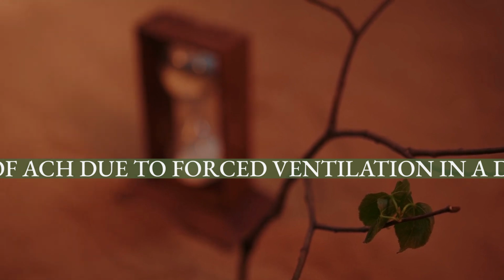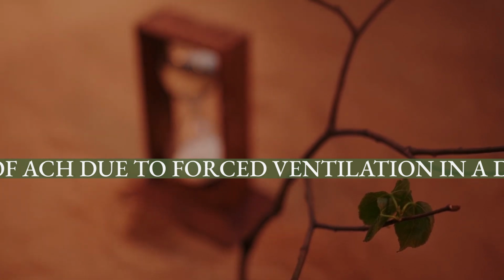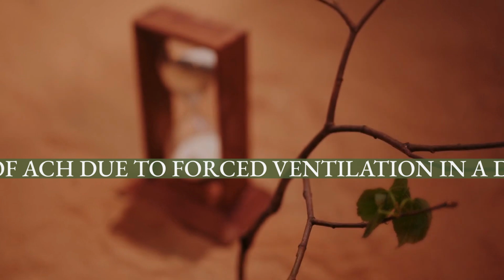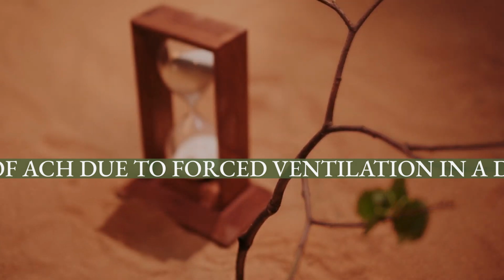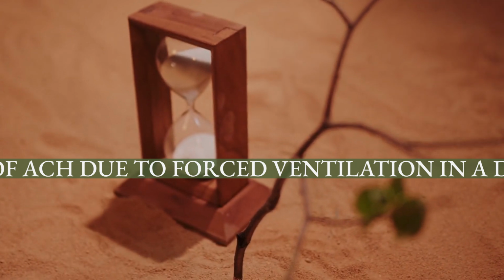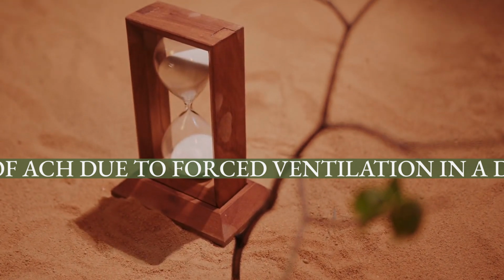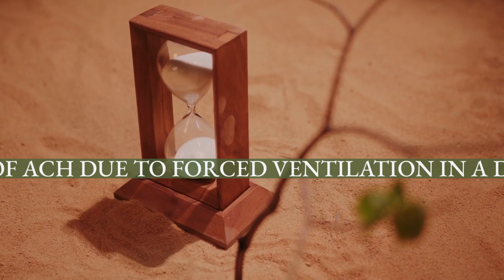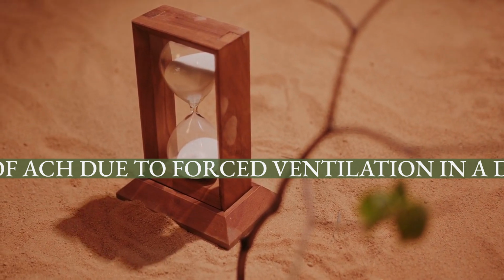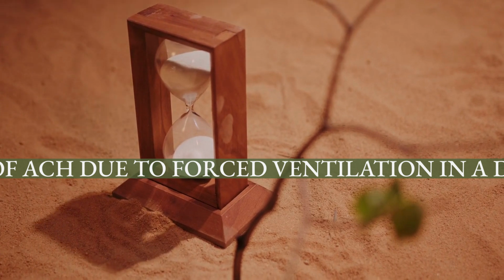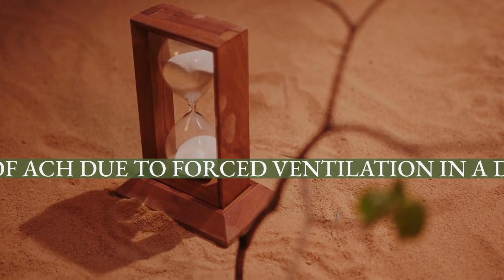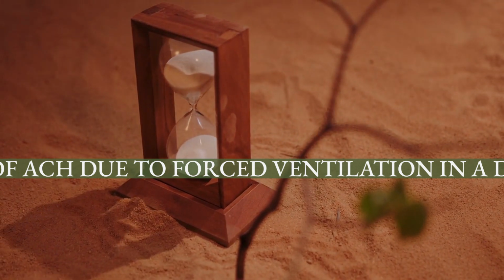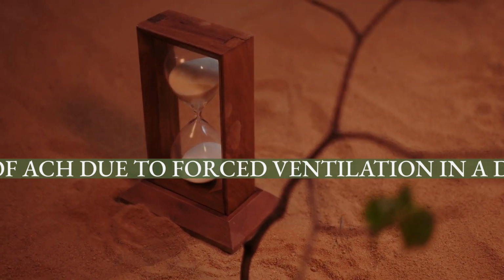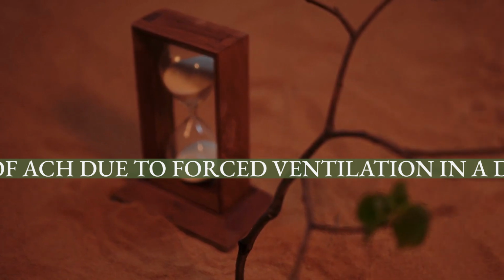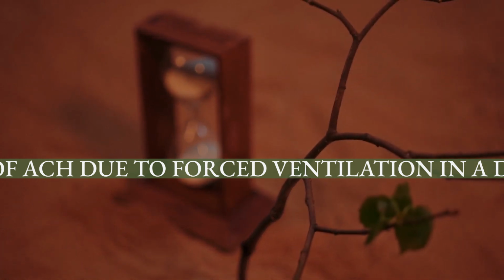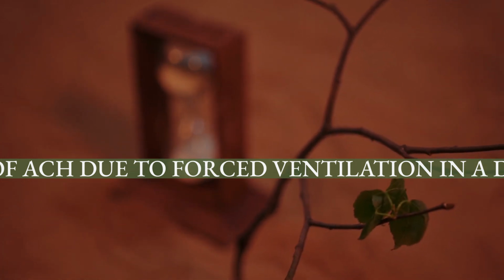7 out of 8 houses studied in NZ in 2010 had an ACPH corrected for ventilation factors of 0.75 or greater. The presence of forced ventilation systems has been shown in some cases to actually increase the humidity rather than lower it. By displacing air inside a dwelling with infiltrated air brought in from outside the dwelling, positive pressure ventilation systems can increase heating requirements in winter or cooling requirements in summer in a house.